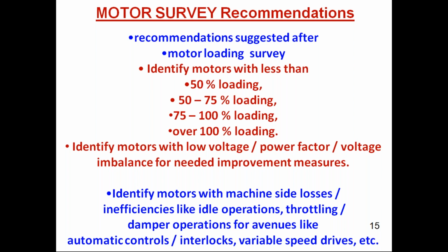This is a typical case for screw compressors throughout India or even in the world. We have seen some 75 kilowatt machines, almost 100 HP screw compressors. A 75 kilowatt motor compressor takes almost 95 to 100 kilowatt. It is running at a 1.2 service factor. That is not supposed to happen.